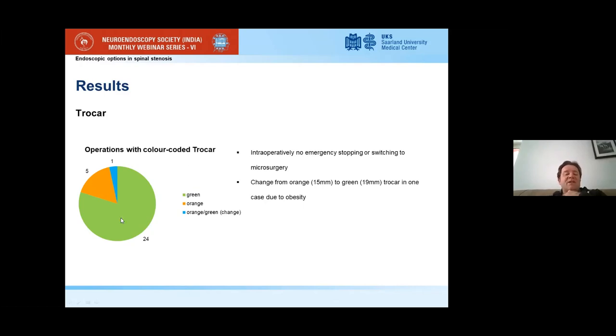This was a very obese patient, and it was just not possible because of the depth of the surgical field with a small trocar to angle the instrument sufficiently. So there wasn't sufficient decompression possible with the small trocar. There was no emergency stopping, no switch to microsurgery.